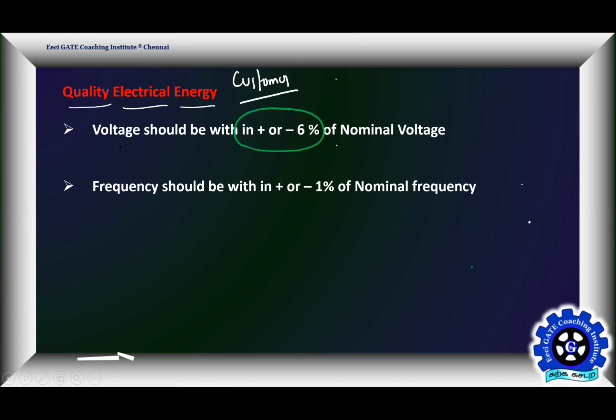The voltage should be within plus or minus 6% of the nominal voltage. That means you should get 230 volt in your plug point. If the voltage is plus or minus 6% of this 230, then I can say that my voltage profile I'm getting is good. Understand? Frequency should be plus or minus 1% of the nominal frequency.